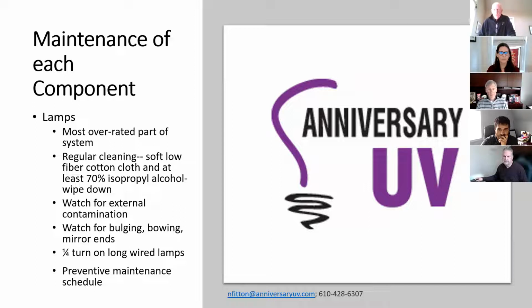So watch for any form of external contamination, watch for bulging, bowing, or mirrored ends. If you have long wired lamps that tend to bow, at each inspection and cleaning, turn that lamp a quarter of a turn. The reason for that is we're trying to offset gravity. So if the low point is at the bottom, I want to move that low point to the side. And next week, I want to move that low point to the top. And then back and forth to try to offset that. That'll help offset bowing.